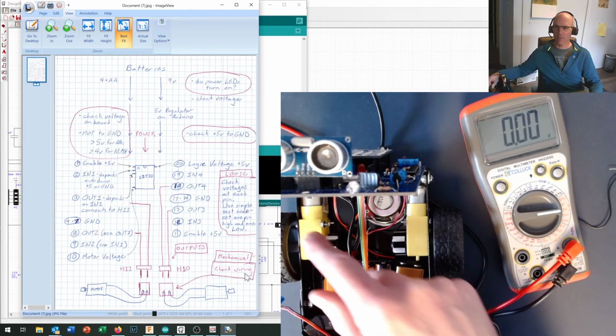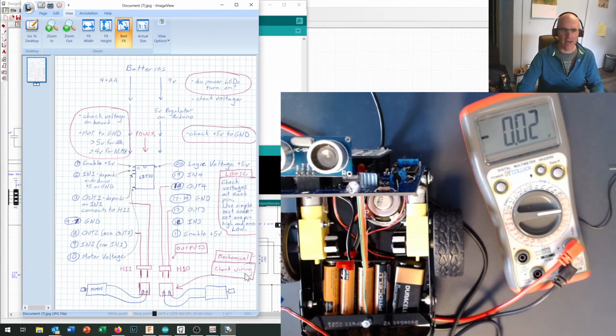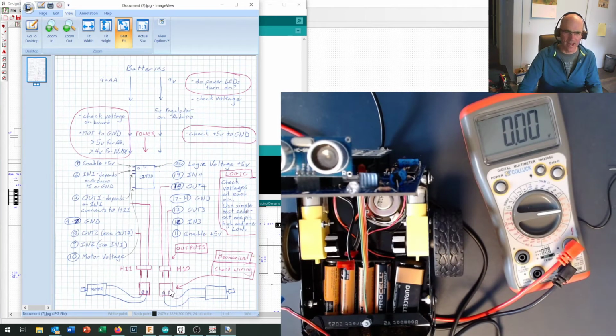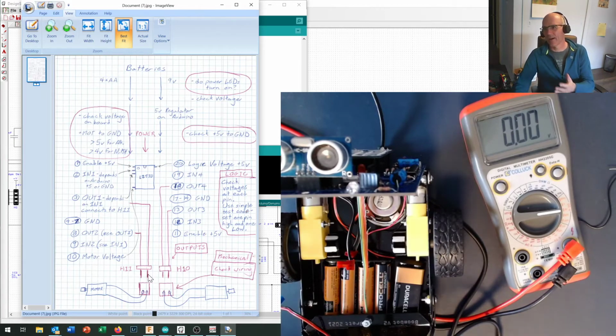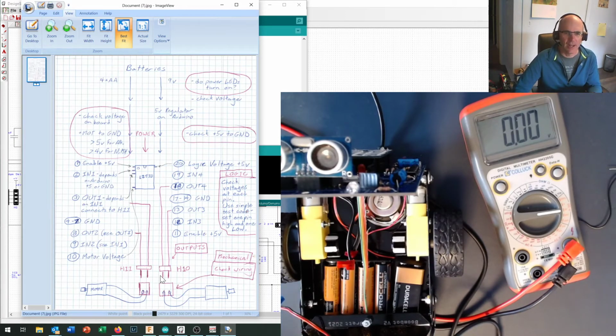You can have a problem with the wiring, bringing that back to its little connector, and you can push those wires in a little tighter. You're not likely to have a problem with these connections right here, but you can unplug your motors and check your voltage outputs at those two terminals. We checked for one motor - you now have to go back and check the other motor to find out what's going on in there, since sometimes one will behave differently from the other.